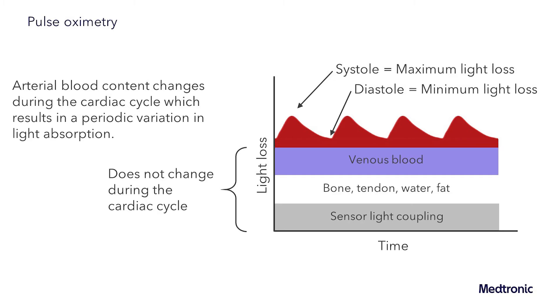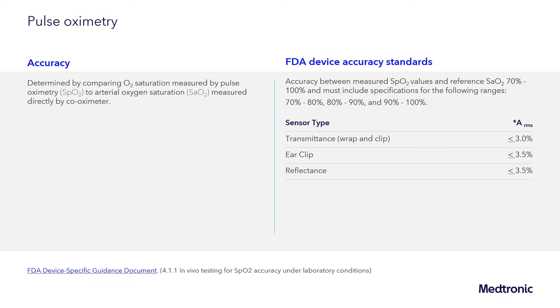Accuracy of a pulse oximeter is determined by comparing the oxygen saturation measured by the pulse oximeter to arterial oxygen saturation measured directly by a co-oximeter. The FDA device accuracy standards require that accuracy between the measured SpO2 pulse oximetry values and the reference SaO2 co-oximeter values be measured and accurate between the ranges of 70 to 100 percent and within the sub-ranges of 70 to 80 percent, 80 to 90 percent, and 90 to 100 percent. The method used to determine accuracy is the accuracy root mean square error, or ARMS.